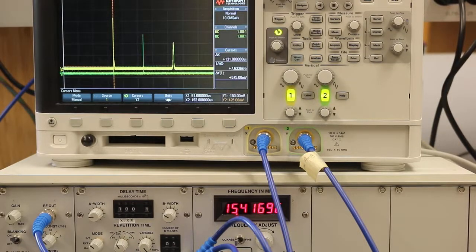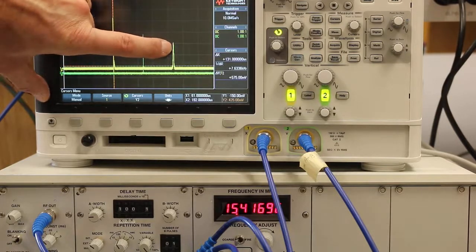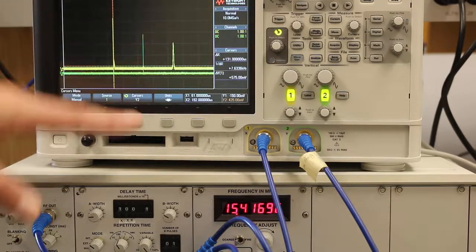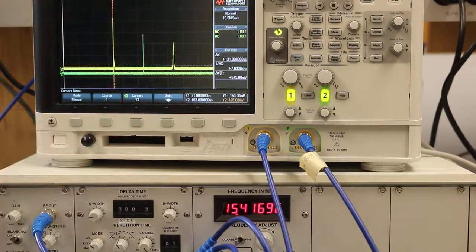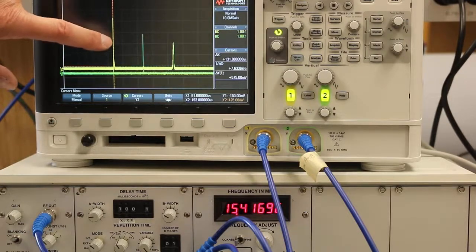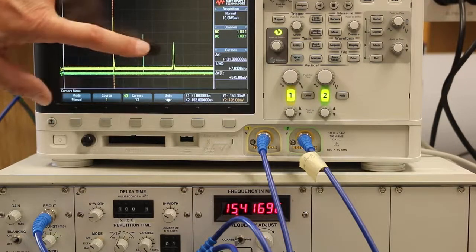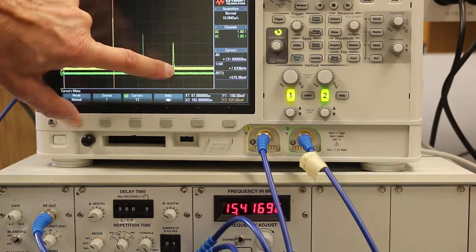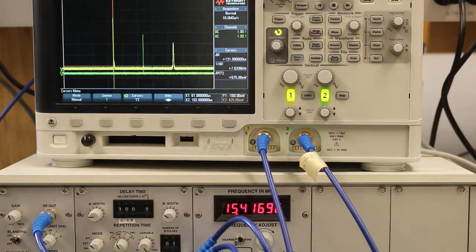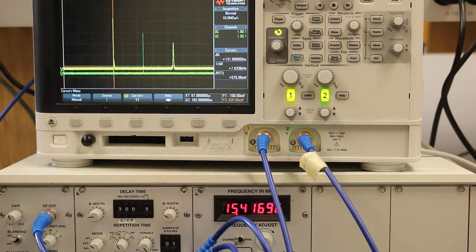So our data in this particular experiment will consist of tracking the amplitude of this signal as a function of delay time between the A and B pulse. So we'll hit it with an A pulse, we'll delay, we'll hit it with a B pulse, and then we'll just see how large the amplitude is of the return signal as a function of delay time. So we'll set that up in the next video. So again, this is our first look at T2 for pulsed NMR, and in the next video we'll actually get some data coming in.